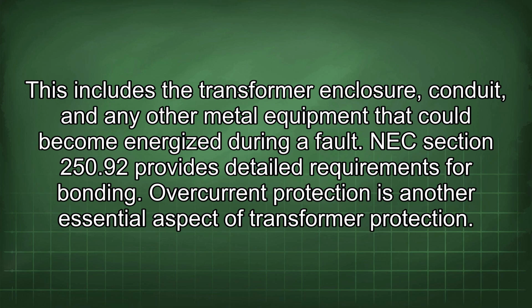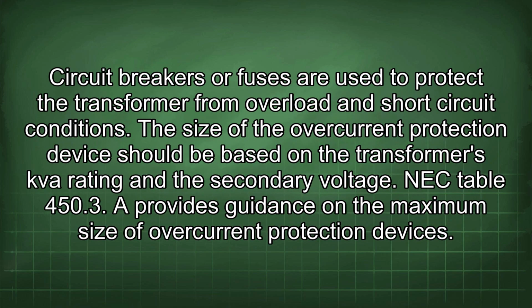Overcurrent protection is another essential aspect of transformer protection. Circuit breakers or fuses are used to protect the transformer from overload and short circuit conditions. The size of the overcurrent protection device should be based on the transformer's kVA rating and the secondary voltage. NEC table 450.3 provides guidance on the maximum size of overcurrent protection devices.